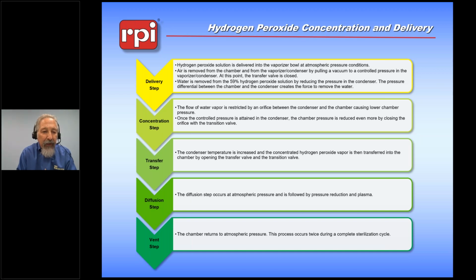We transfer that concentrated hydrogen peroxide into the chamber. We allow it to diffuse through the instruments, getting into the various lumens and hinges of these instruments, and then we will vent it out after we have reduced the hydrogen peroxide, and we have turned what remaining peroxide into water and free oxygen.